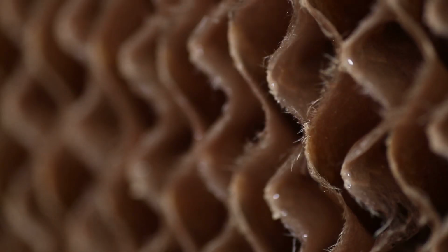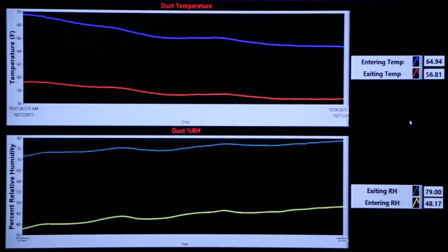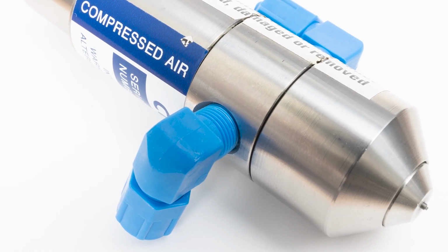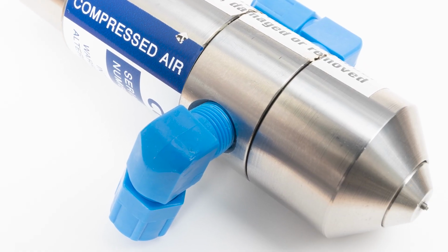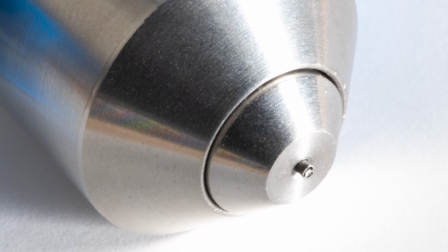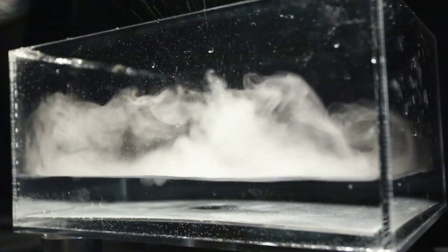You can drip water across a pad, wicking it away as the air moves across it. A different way of doing it, a way of media. You could do compressed air. Instead of pressurizing it really high, you could use a compressor that's under pressure along with the water and shatter it to small particle sizes. Otherwise, you can agitate water, vibrate water really rapidly and cause it to basically become a fine mist, and that's ultrasonic. All different ways, and what the particle size is changes, and what utilities you need in order to be able to do that. Sure.